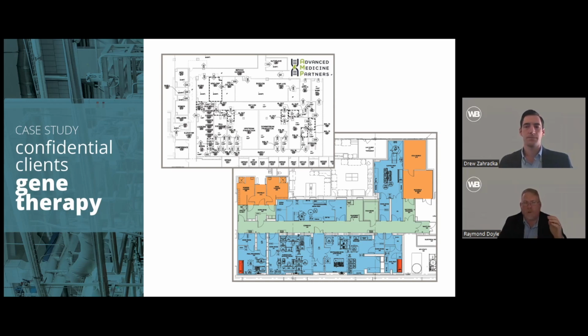And I always say the smart solution is a lot like maintaining safety in front of a fume hood. Because if you're doing 75 to 100 feet a minute, you're maintaining a pretty constant flow at a reasonable velocity. So as long as you move with a methodical purpose and you don't jump around and run across the room or move real quickly, as long as you move slowly with purpose, the airflow will continue to move in the direction you want it to go, and the particles will generally carry with it. So that's really part of that standard of maintaining the face velocity off of those fan-powered HEPAs or filtered HEPAs at the surface of the wall or the ceiling.